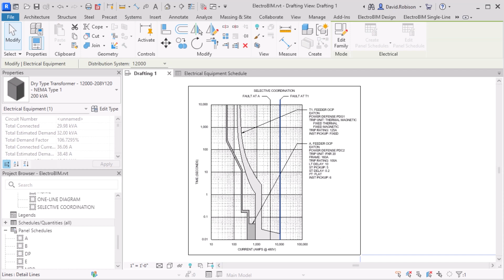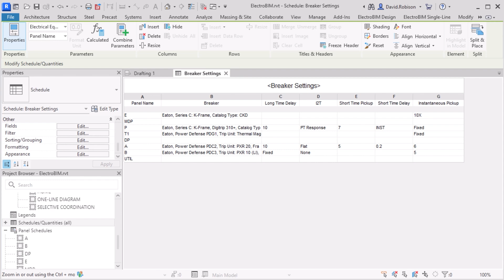We added the ability to link Revit shared parameters to ElectroBIM information so you can transfer that data to our add-in more easily. And we added shared parameters for breaker settings so you can schedule those settings in Revit. Previously you were limited to showing that on your trip curves, but now you can actually show it in Revit schedules. Those are the kinds of features we've been adding over the last year.